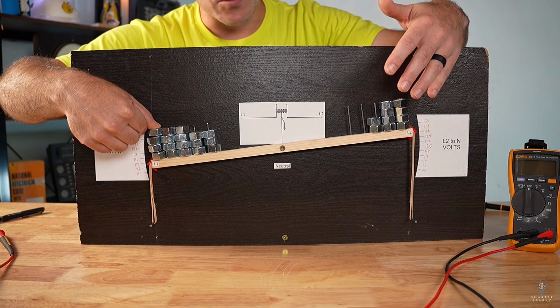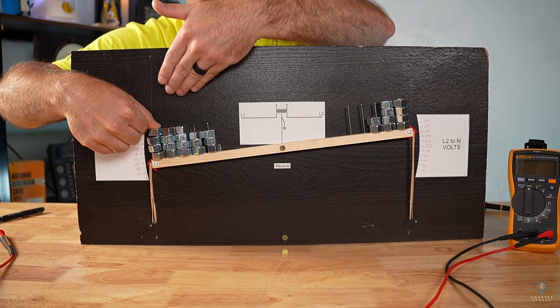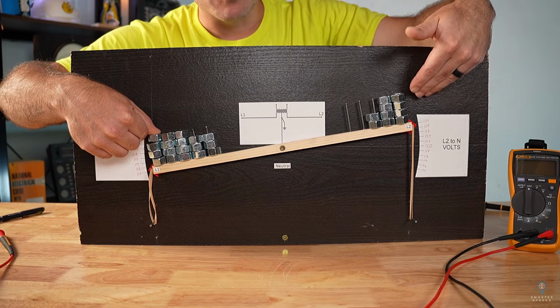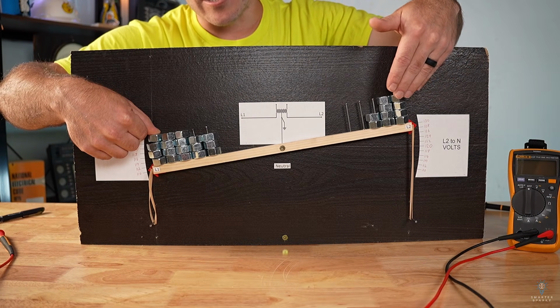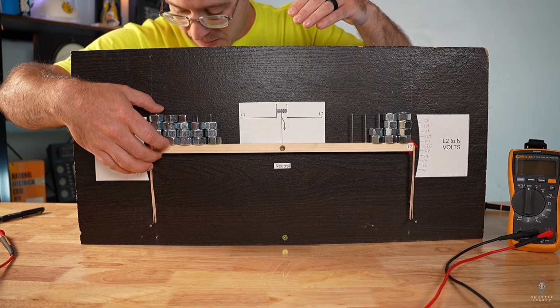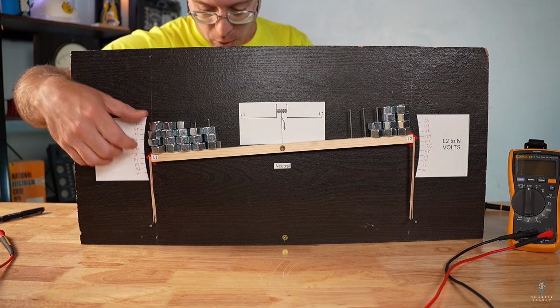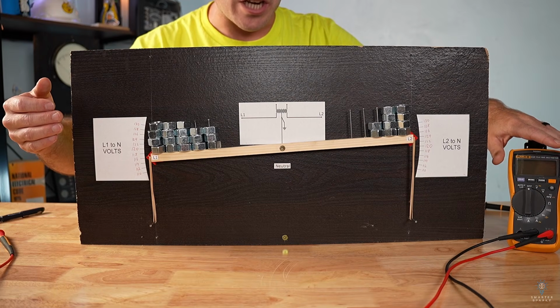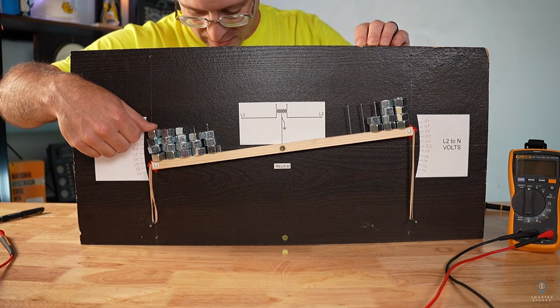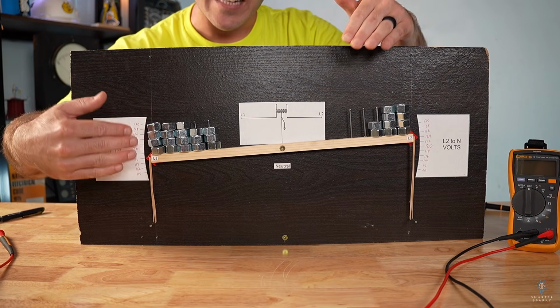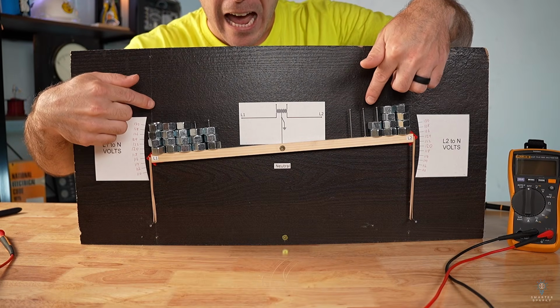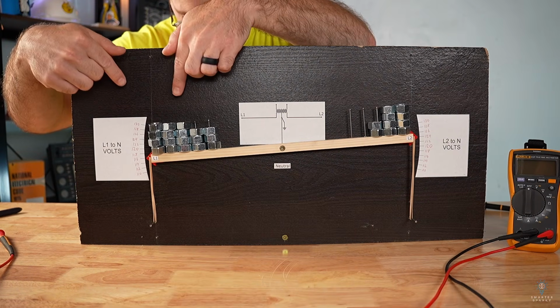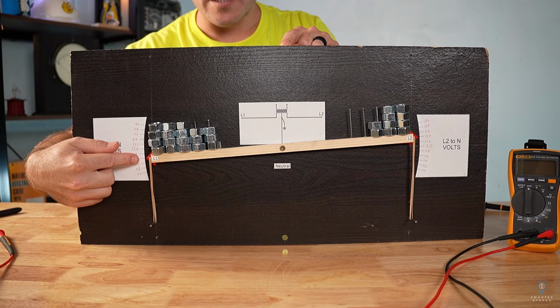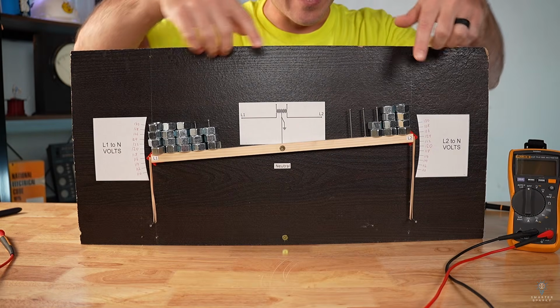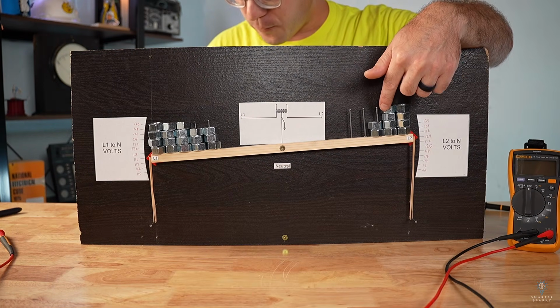That's why having that multimeter with the min-max value was able to show us those absolute minimum voltages and those absolute maximum voltages. Because when those motors start up, that inrush current is very fast. And then things actually bounce back to what their running current is. So just watching that meter change voltages, we're going to be missing those massive increases when that motor kicks in. And that's where we got that massive spread. So when this happens, any lights that are on this line are going to see a lower voltage, which will make them appear dimmer. Any lights that are on this line are going to see a higher voltage and they're going to seem brighter. Let's clarify a few things real quick.